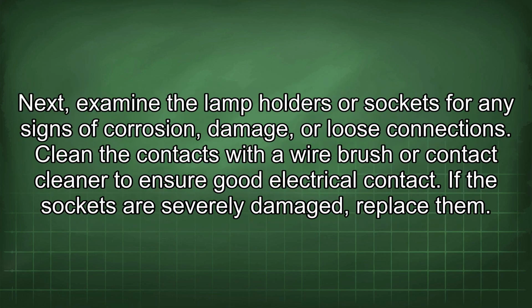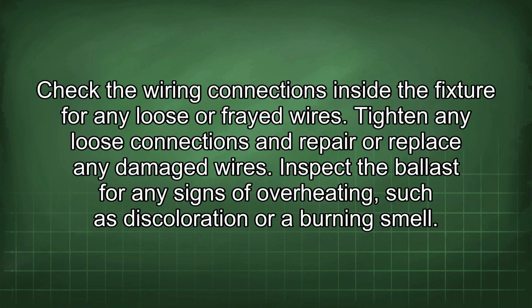Next, examine the lamp holders or sockets for any signs of corrosion, damage, or loose connections. Clean the contacts with a wire brush or contact cleaner to ensure good electrical contact. If the sockets are severely damaged, replace them. Check the wiring connections inside the fixture for any loose or frayed wires. Tighten any loose connections and repair or replace any damaged wires. Inspect the ballast for any signs of overheating, such as discoloration or a burning smell.